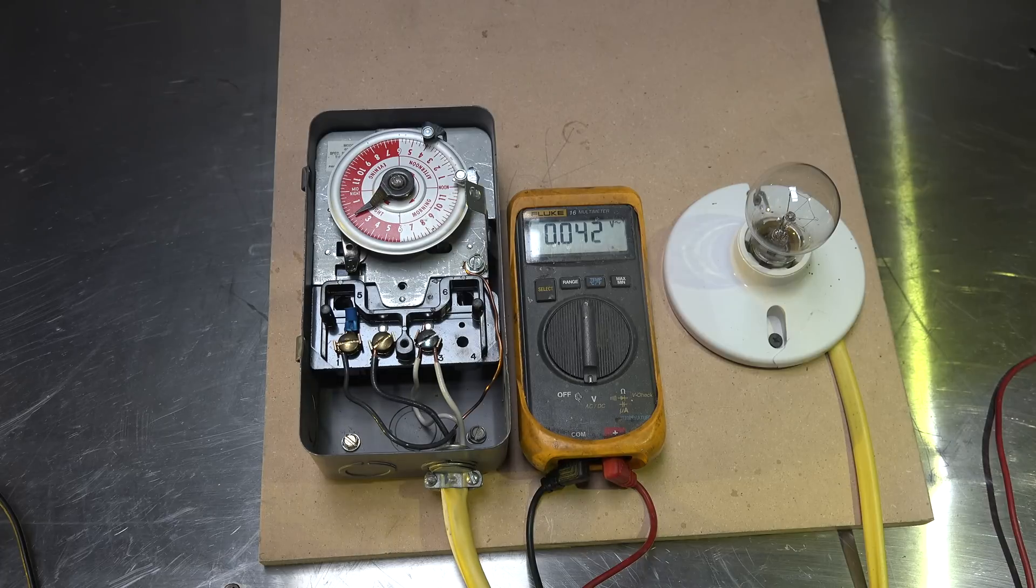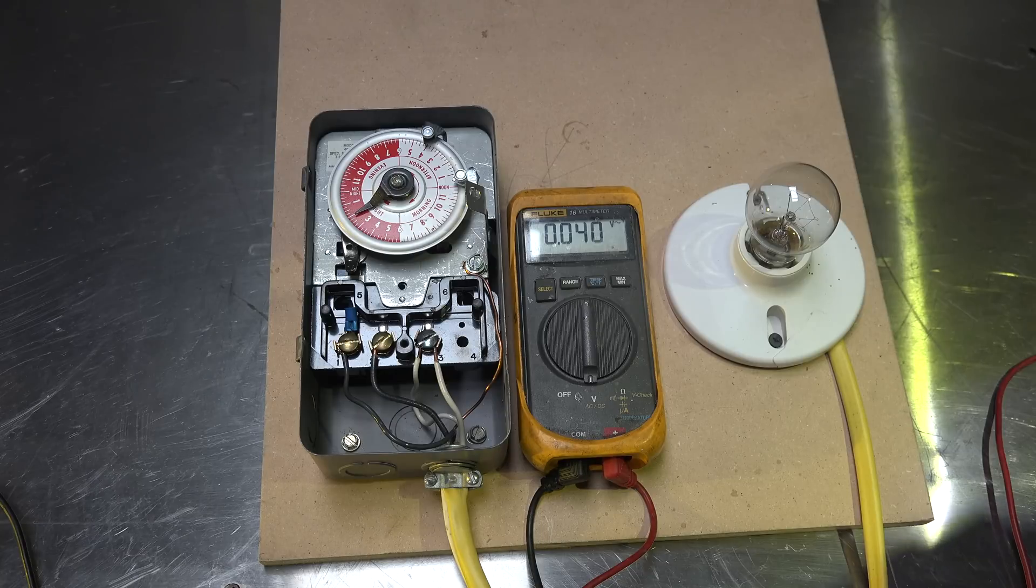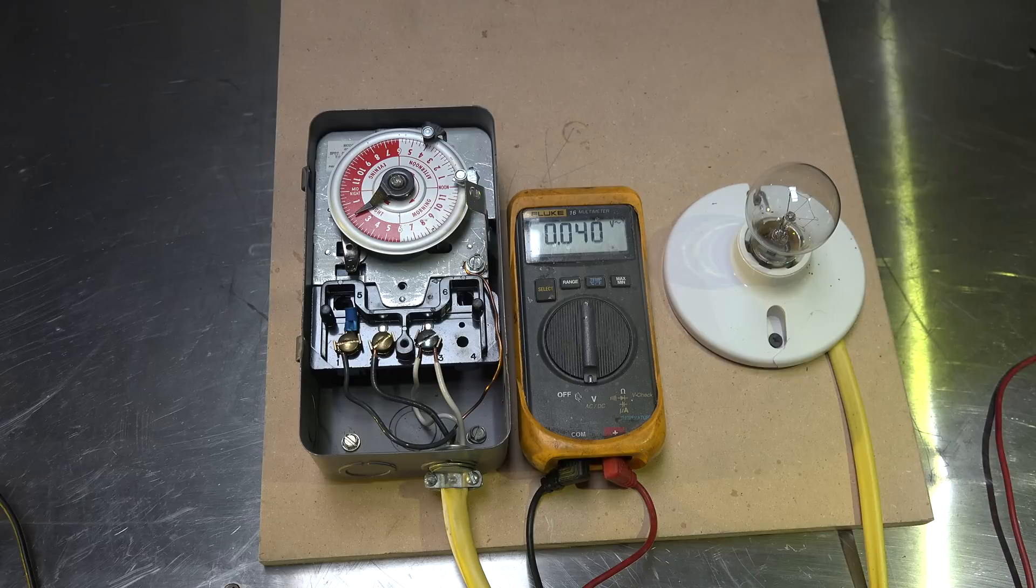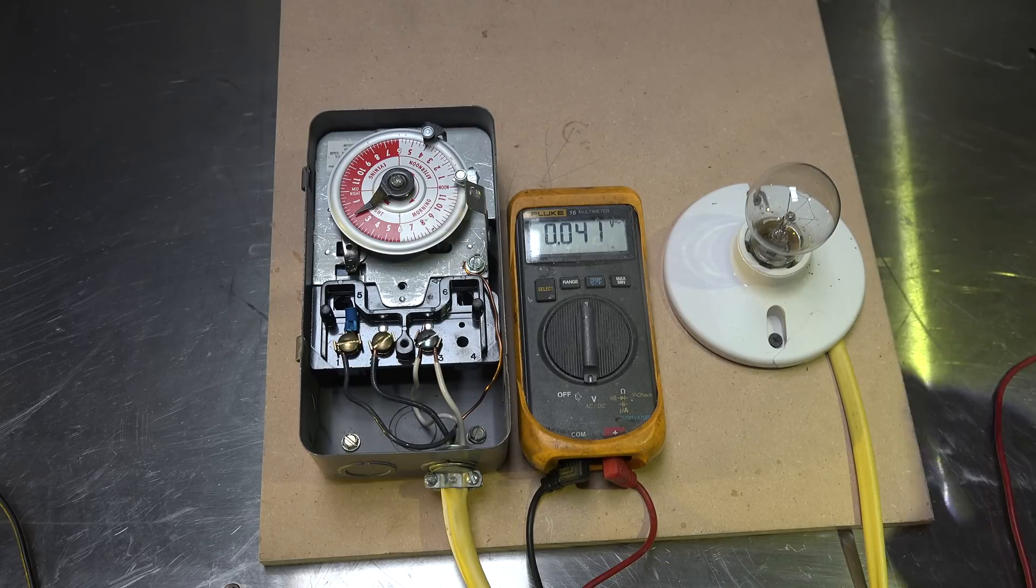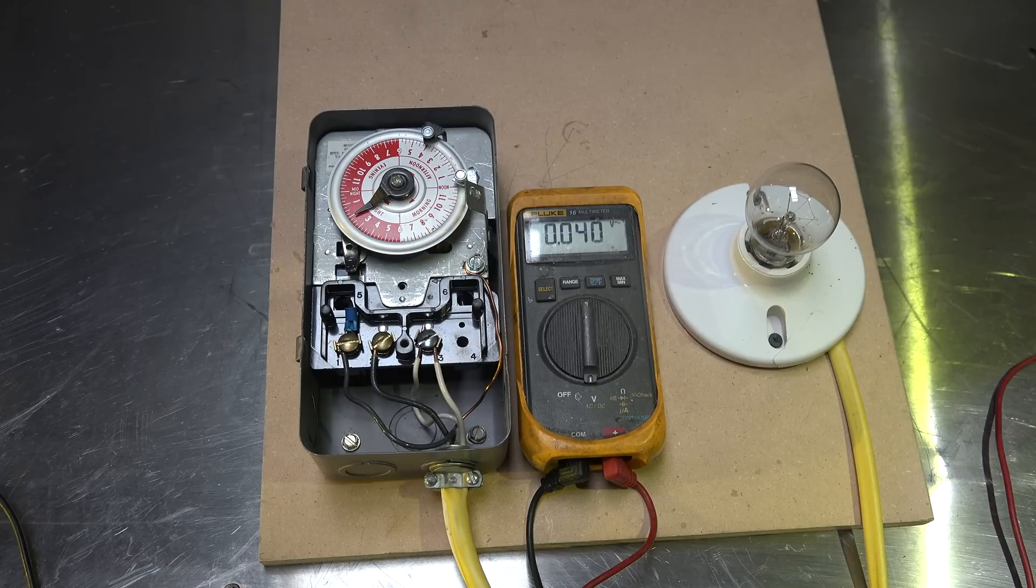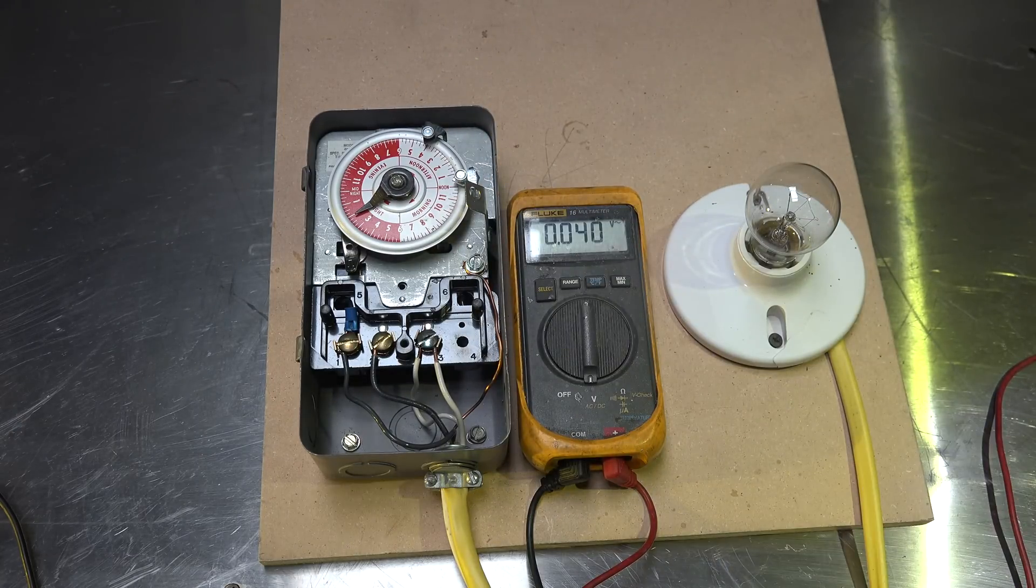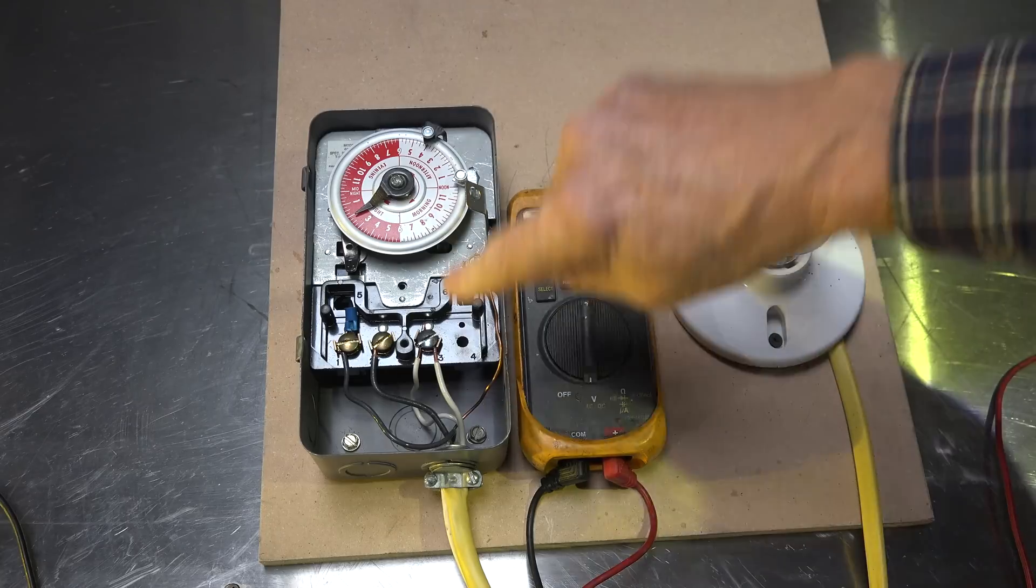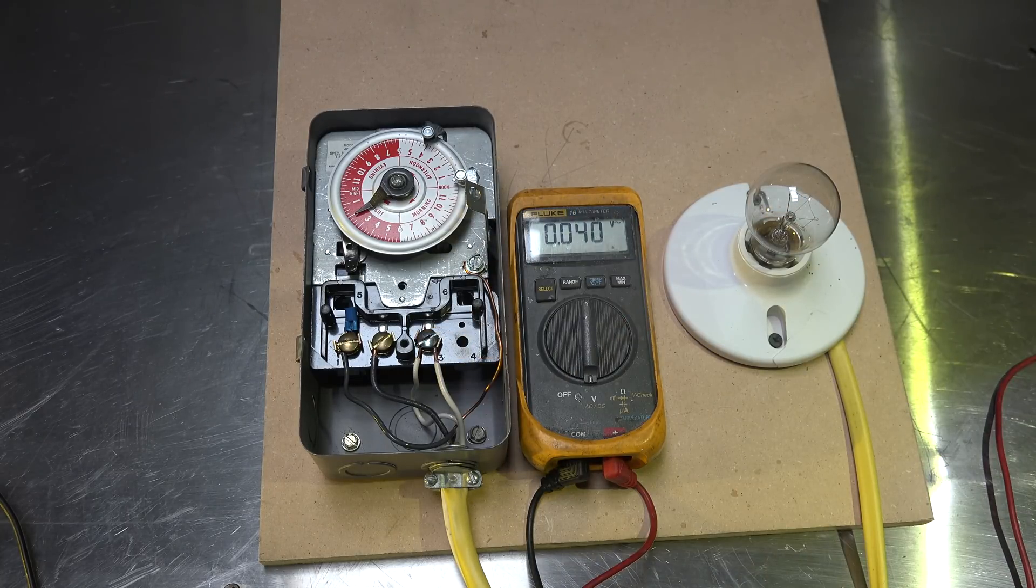I noticed a number of people were asking me questions about grounding and neutral and why it was not okay. This is a 110 volt sub panel. Why was it not okay to jumper from the chassis ground—the box with the wire right there, the safety ground—and the neutral? Because they go to the same place back at the panel.